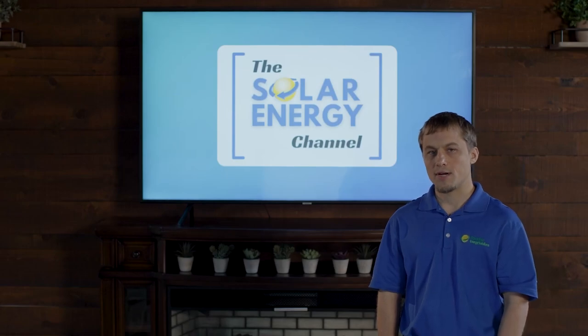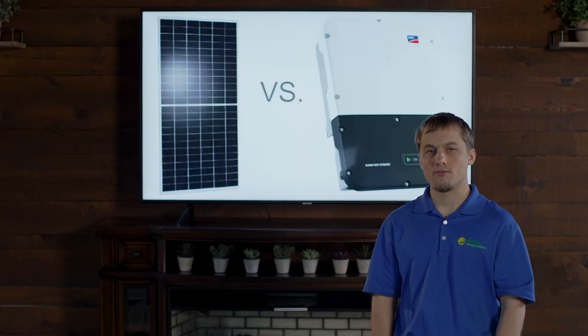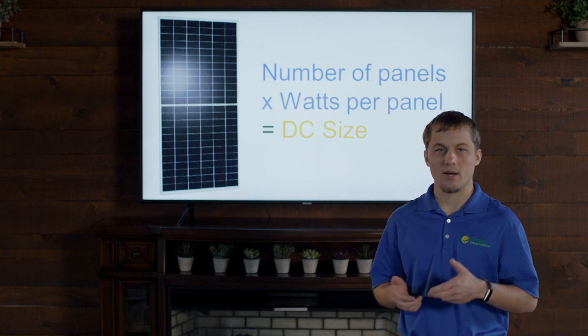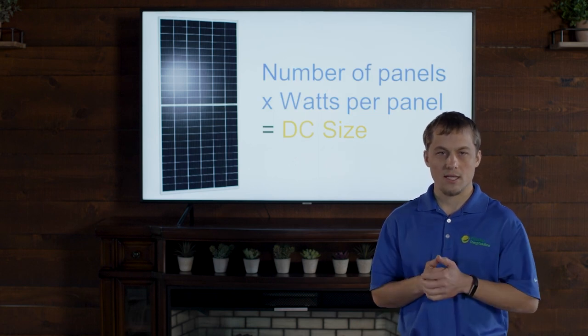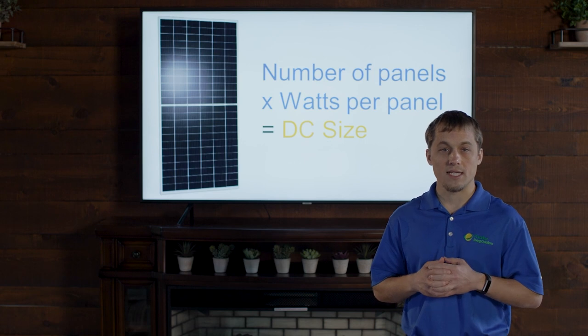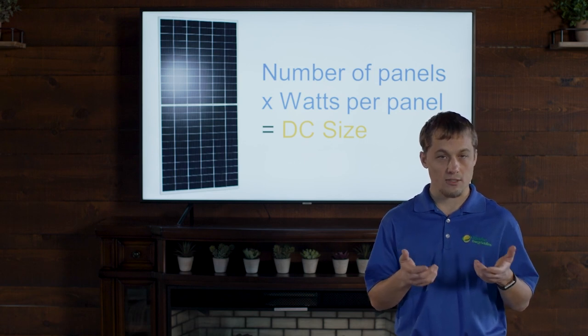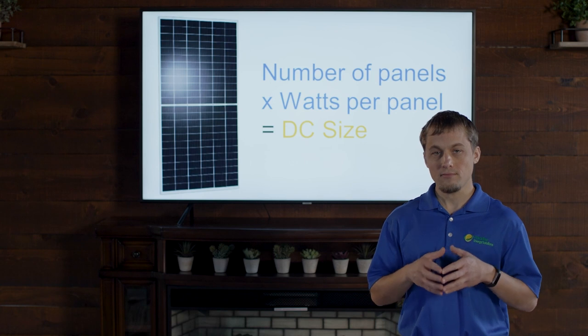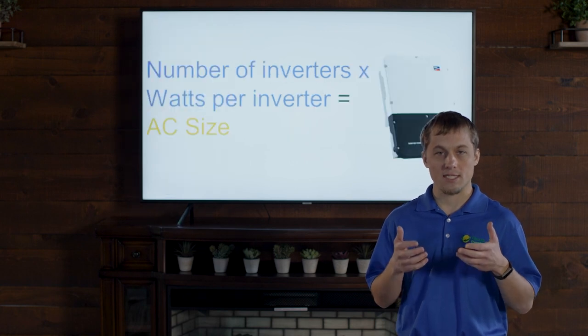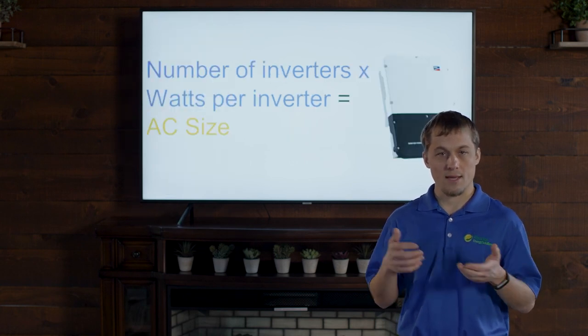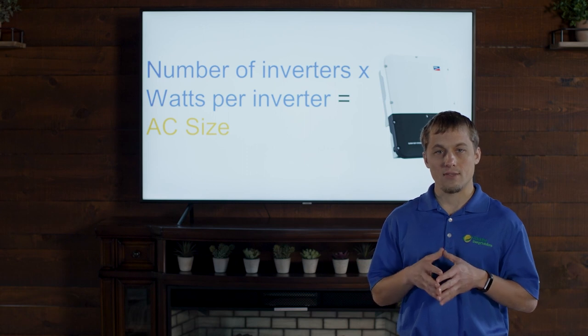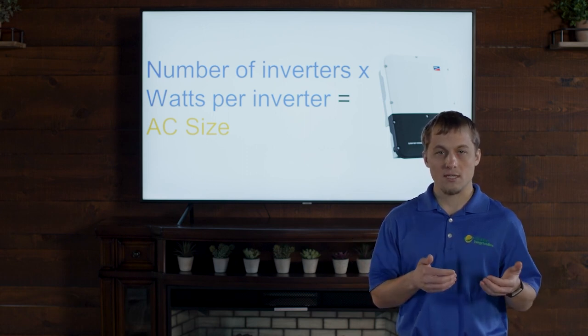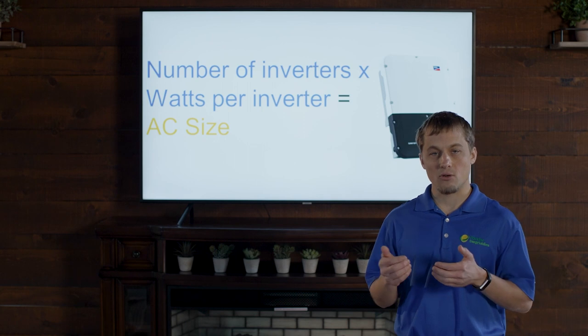The DC-AC power ratio is found by taking the number of DC watts in a system divided by the number of AC watts in the system. The DC watts is found by taking the number of modules or solar panels times the watts per panel, and the AC watts is found by taking the number of inverters times the watts per inverter. You get the DC-AC power ratio by taking the total DC watts divided by the total AC watts.